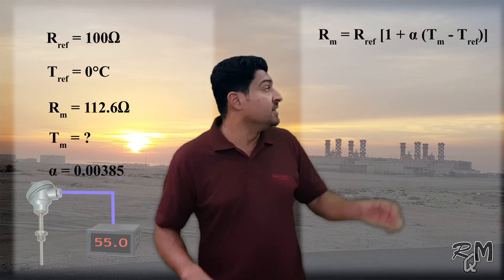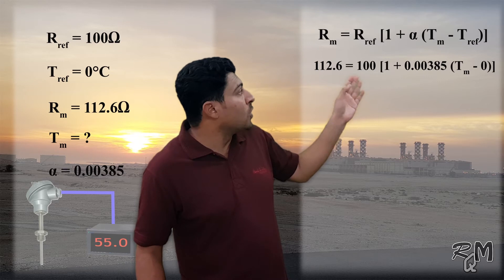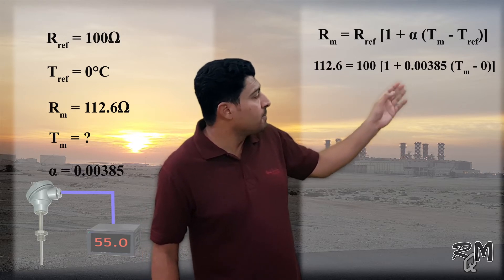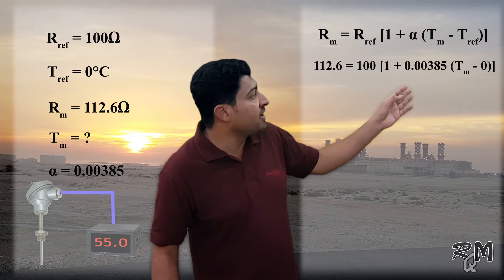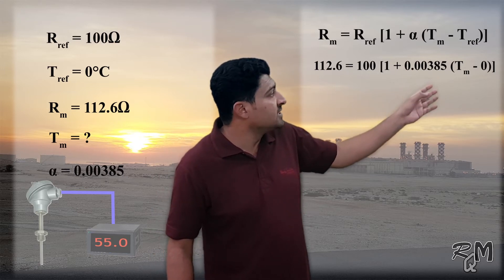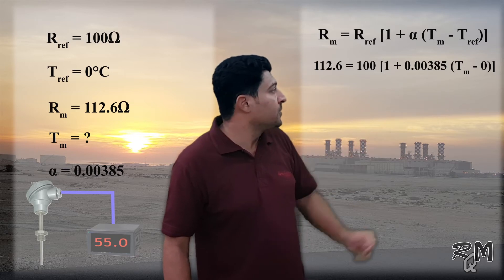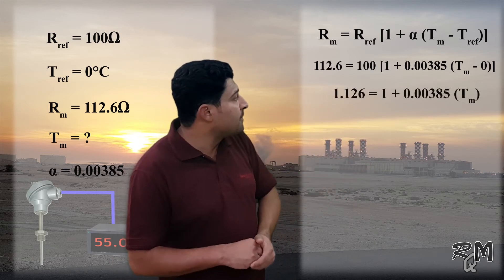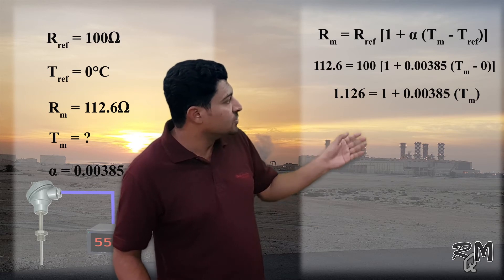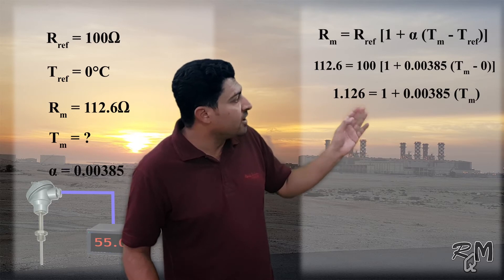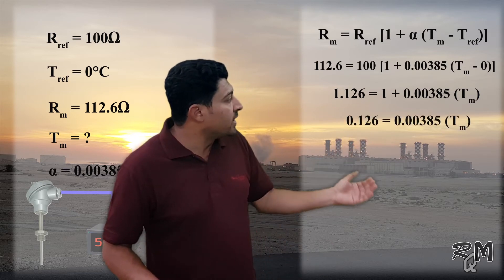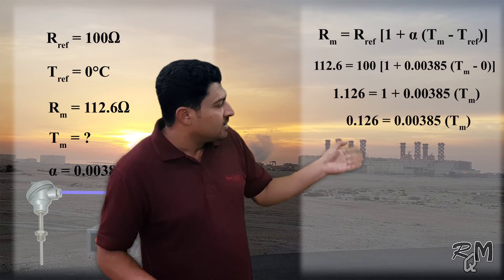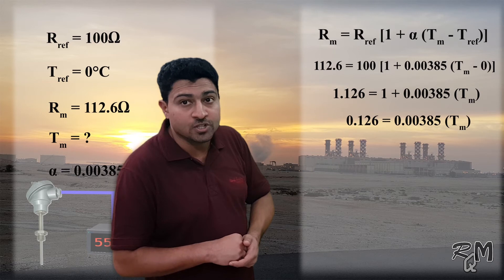Now I will insert these values into the equation. The measuring resistance 112.6 ohms equals the reference resistance 100 ohms, times the square bracket 1 plus alpha 0.00385, multiplied by the measuring temperature minus the reference temperature 0 degrees centigrade. I will solve this equation for measuring temperature. Bringing 100 ohms to the other side, it becomes 1.126 equals 1 plus 0.00385 multiplied by the measuring temperature.